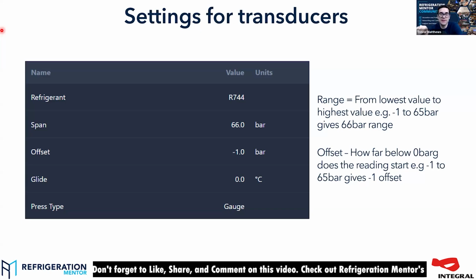I've seen this. I was in a CO₂ training last week in one of my groups, and the guy said he went to the case and put his gauge on, and it was reading, I think we said, 20 psi off. What is going on here? The transducer must be failed. Went out, picked up another transducer, came back, put it on, and it was still reading 20 psi off. And then he was like, well, what do I do?